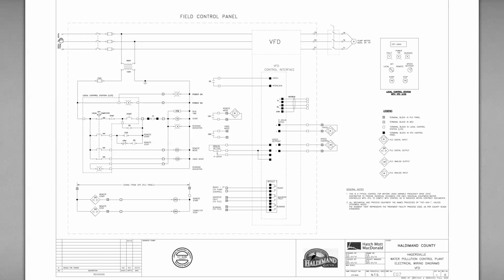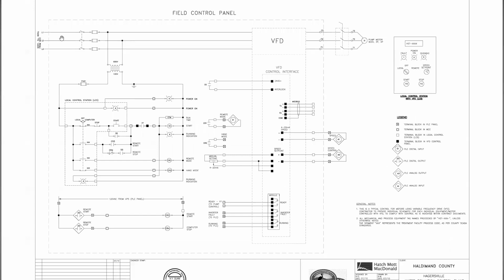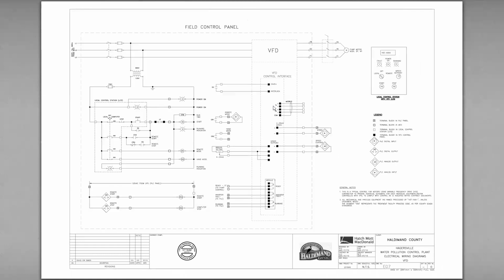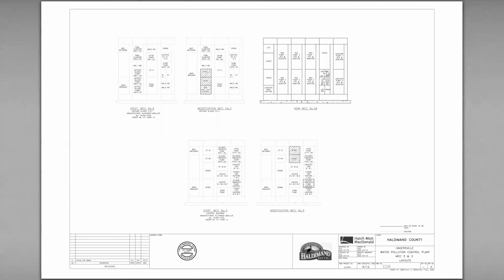So you can see here, this is where you get 600 volts. So this would happen inside the MCC. This would not be in a PLC control panel, but it's important as a controls programmer to know what's going on inside these MCC buckets. So this VFD would actually live, I say live like it's alive, inside one of these. So let's say it's a RAS pump, return activated sludge pump, VFD, and reactor.